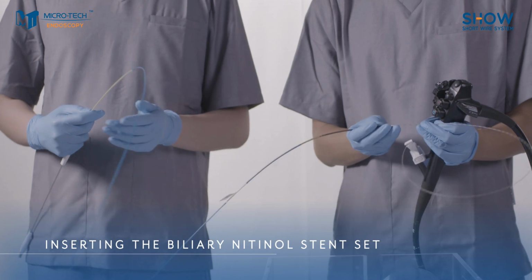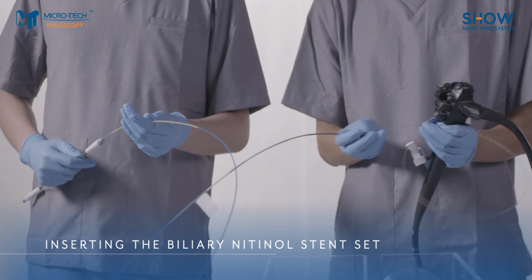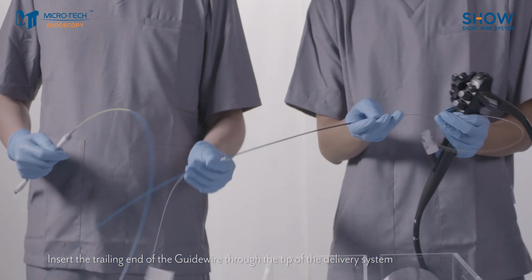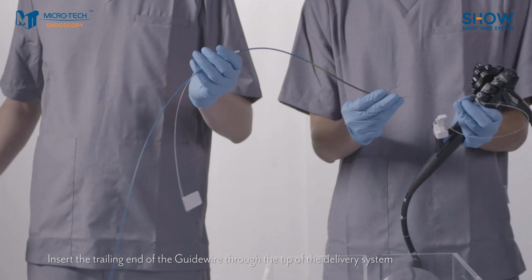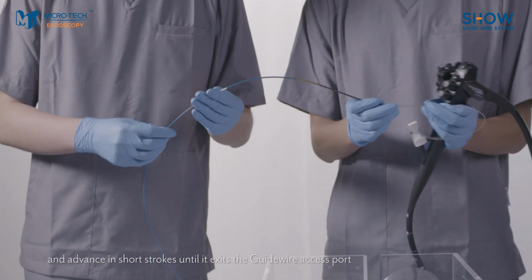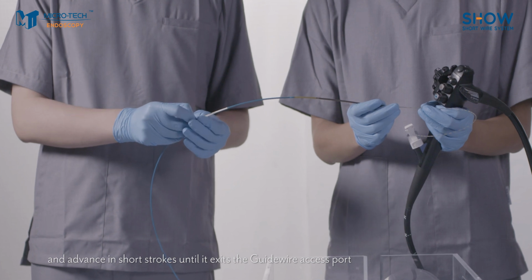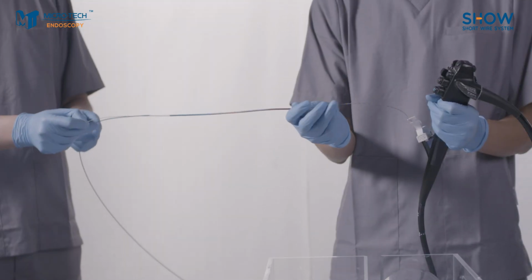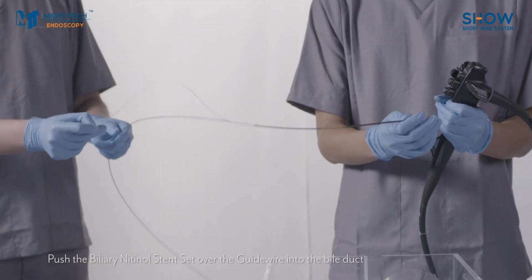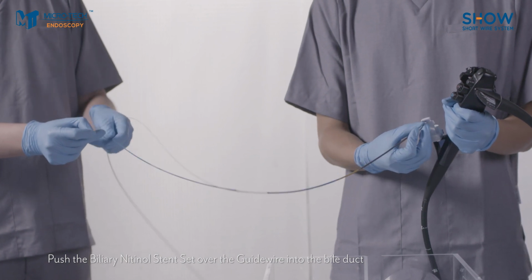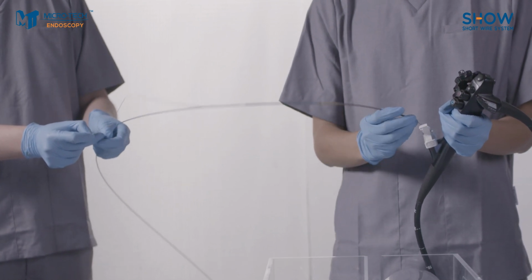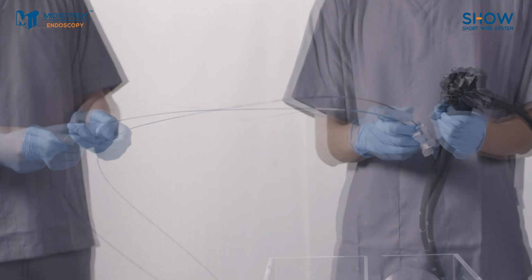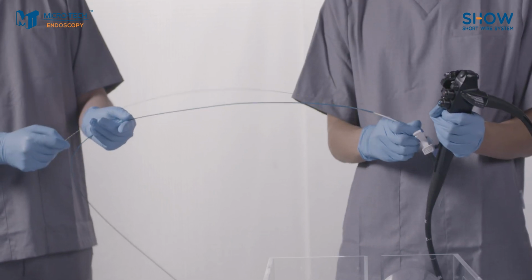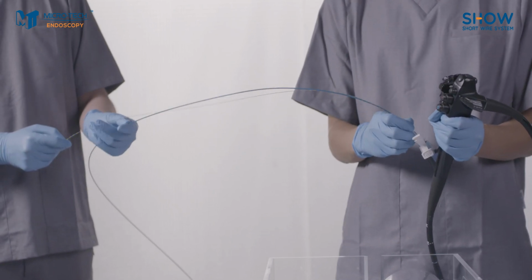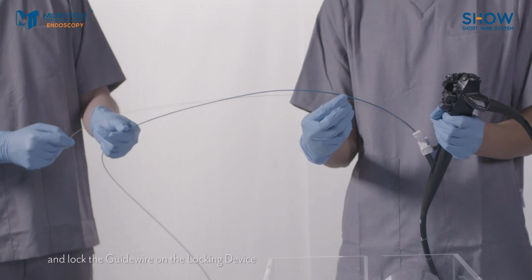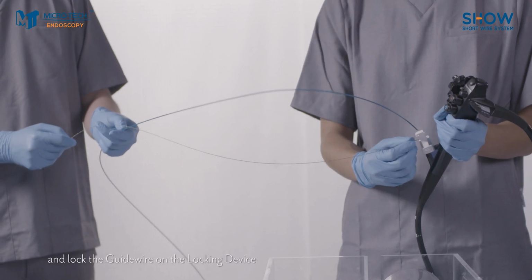Inserting the biliary Nitinol stent set. Insert the trailing end of the guide wire through the tip of the delivery system and advance in short strokes until it exits the guide wire access port. Push the biliary Nitinol stent set over the guide wire into the bile duct and lock the guide wire on the locking device.